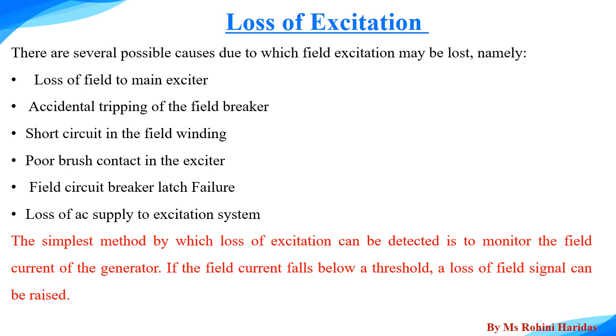The simplest method by which the loss of excitation can be detected is to monitor the field current of the generator. If the field current falls below the threshold, a loss of field signal can be raised.